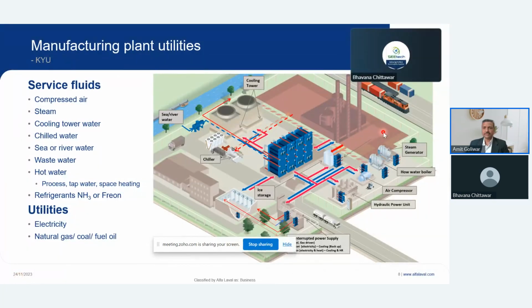To know the utilities first: if you look at any process plant, you will have some heating media, so probably a steam generator or a hot water generator. Compressed air is used in a lot of processes and even to drive instruments and valves. Many processes need a hydraulic power unit. For refrigeration, sometimes you need ice storage or a chiller, and there is cooling tower water in a lot of processes. To ensure there is uninterrupted power supply, many process plants will have either a captive or cogeneration power plant or their own generation. Sometimes plants near a river may even utilize filtered water for the process. So a normal plant will have compressed air, steam, cooling tower water, electricity, natural gas, or even fuel.